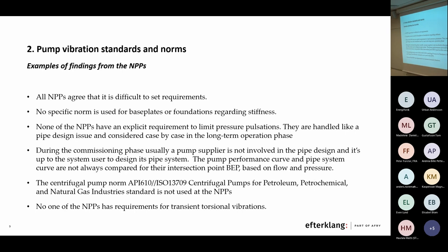And as you know, I can just say something about the foundations. The foundation is extremely important because you can tune your bending modes of the pump system with the foundation. It's like an instrument, like a guitar. Depending on how stiff your base plate is, you can set your bending modes very much where you want to have them. But you cannot set your torsional modes. That's very important to know. The torsional modes you cannot tune with the base plate. That's why you need to have a torsional calculation of the pump unit.